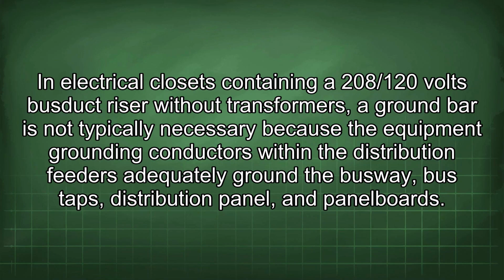In electrical closets containing a 208/120 volts bus-duct riser without transformers, a ground bar is not typically necessary because the equipment grounding conductors within the distribution feeders adequately ground the busway, bus taps, distribution panel, and panelboards.